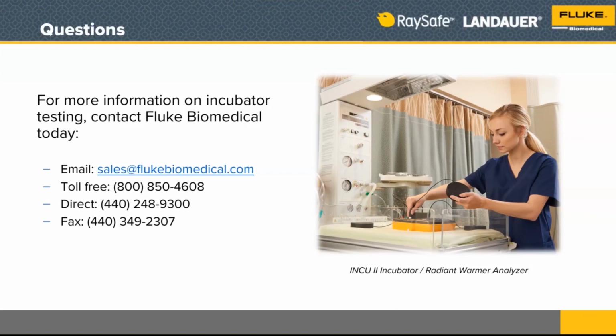So one of the questions around temperature was, what if we're in a hot country where ambient is already a little high and the rise time or the 11 degrees you're talking about over the incubator spec? Yeah, so that's a really good question, and that has come up a lot in tropical climates in particular. Especially in Thailand, when we first launched this product, it came up immediately. We had a biomed department that was in a remote area, and they did not have a shop that was temperature controlled, so they didn't have air conditioning. They were just at whatever the temperature was. And the temperature out in those areas of the world is very warm already. And indeed, you do not have 11 degrees C between the ambient temperature and the set temperature of the incubator. So that test then can't really be done exactly the way that it's written in the standard.